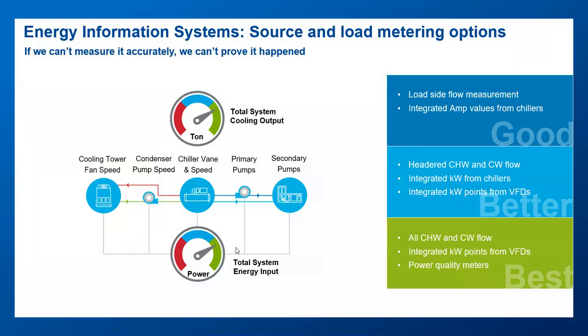So in tackling your plant, you want to look at those three categories that the LBNL team talked about in their hierarchy. The first step is energy information systems, because you can't manage what you don't measure. So what we've done here, for a typical water-cooled chilled water plant, is set up a good, better, best framework for how you might think about getting the energy information systems or the sub-metering in place that needs to be there.